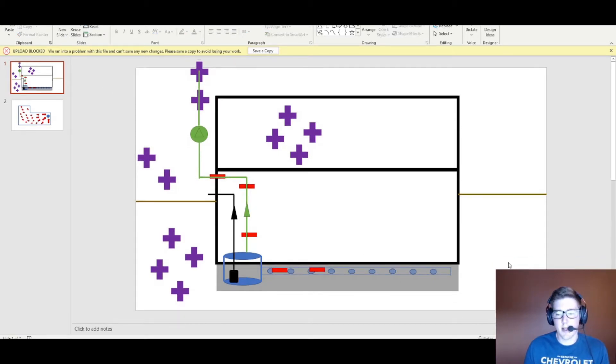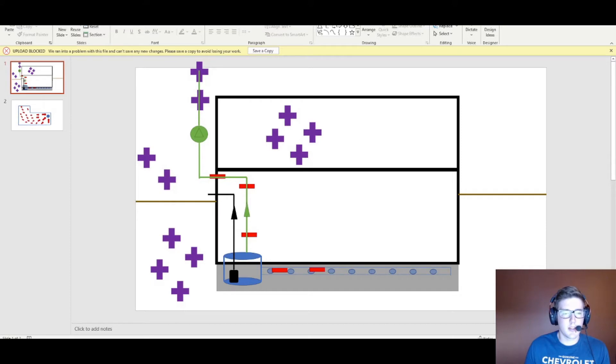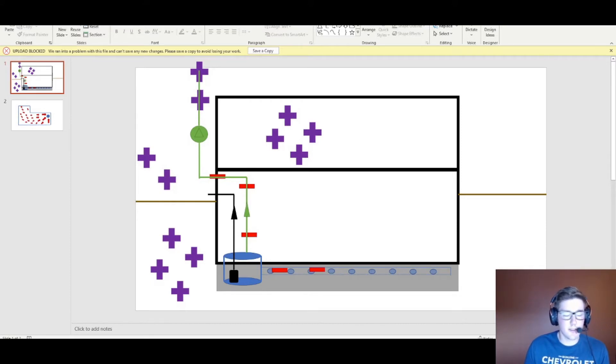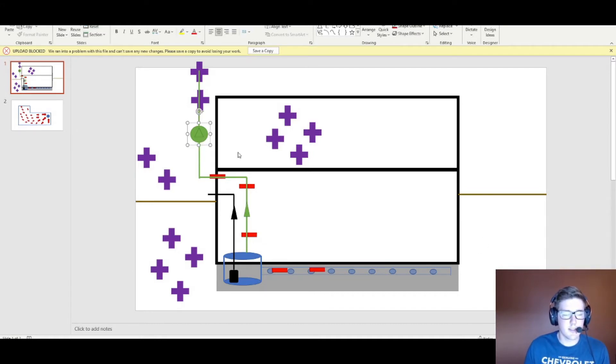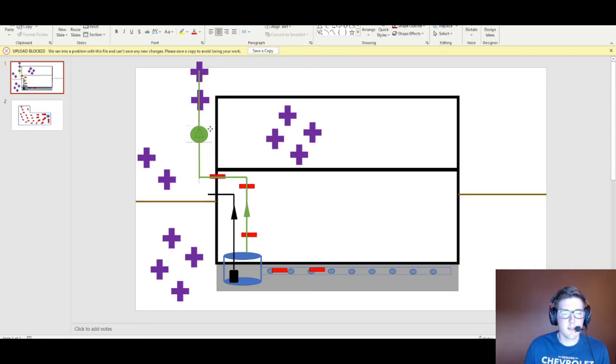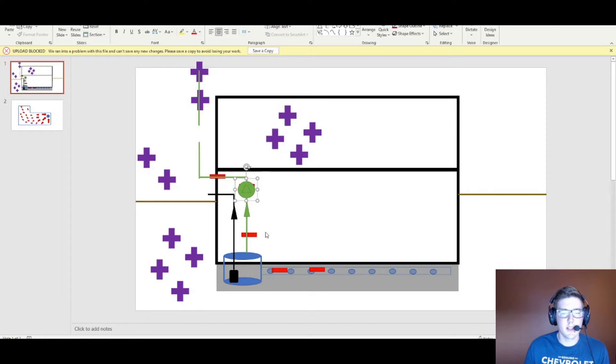I think there's a radon mitigation code that you really should follow if you're going to do this install yourself, and that is to make sure you put the fan outside. The reason for that being if you install the fan inside your house and that fan housing or a fitting has a leak on the discharge side.